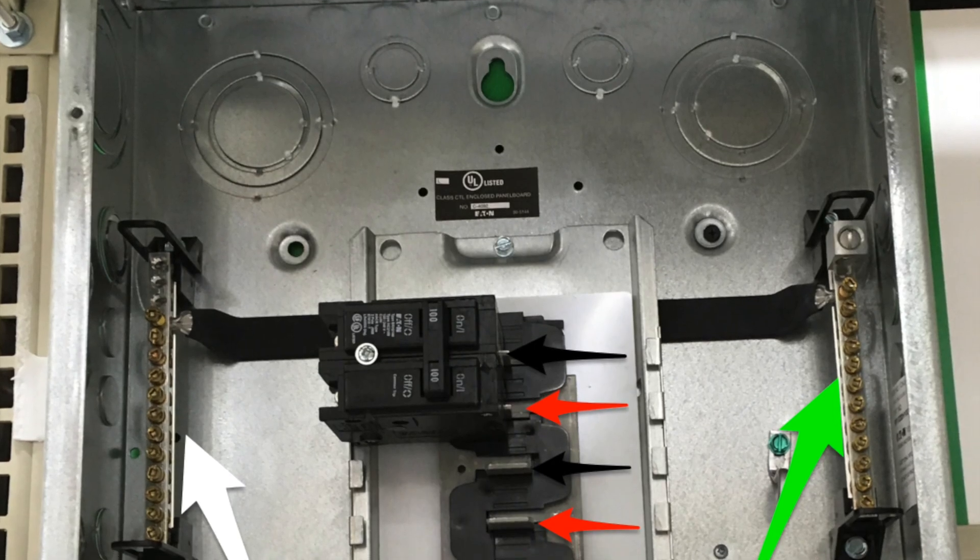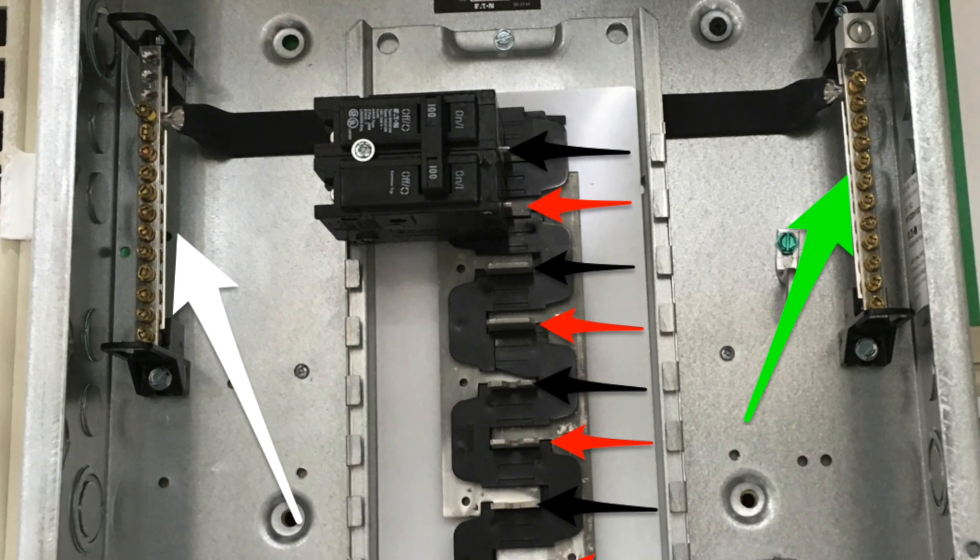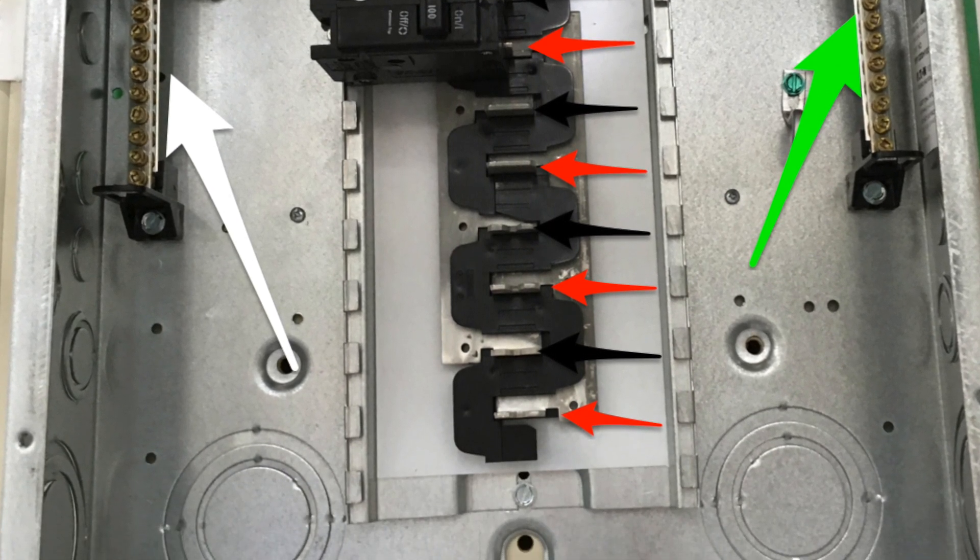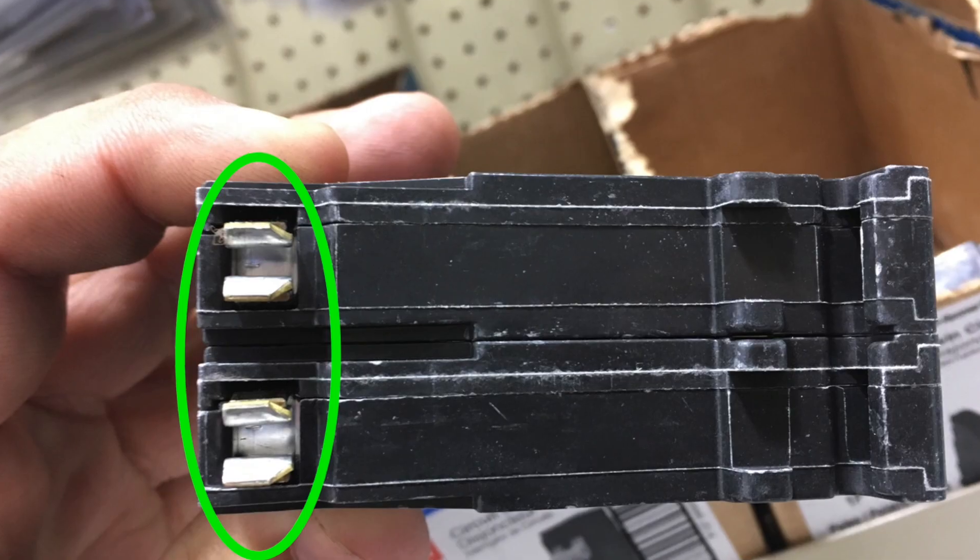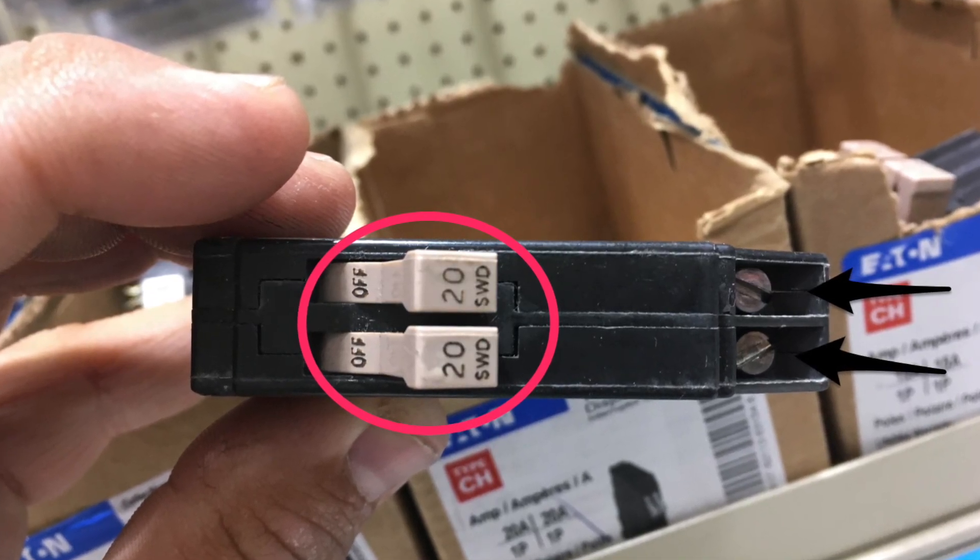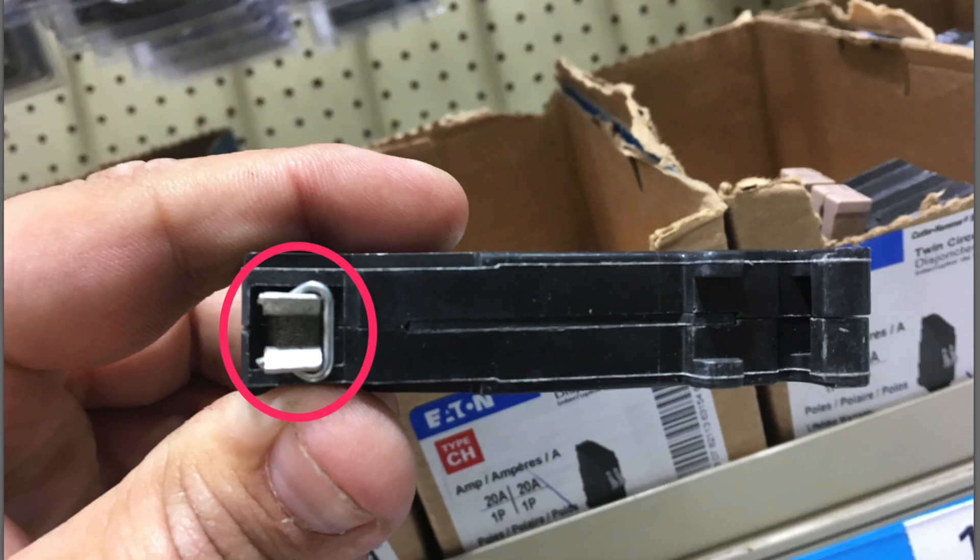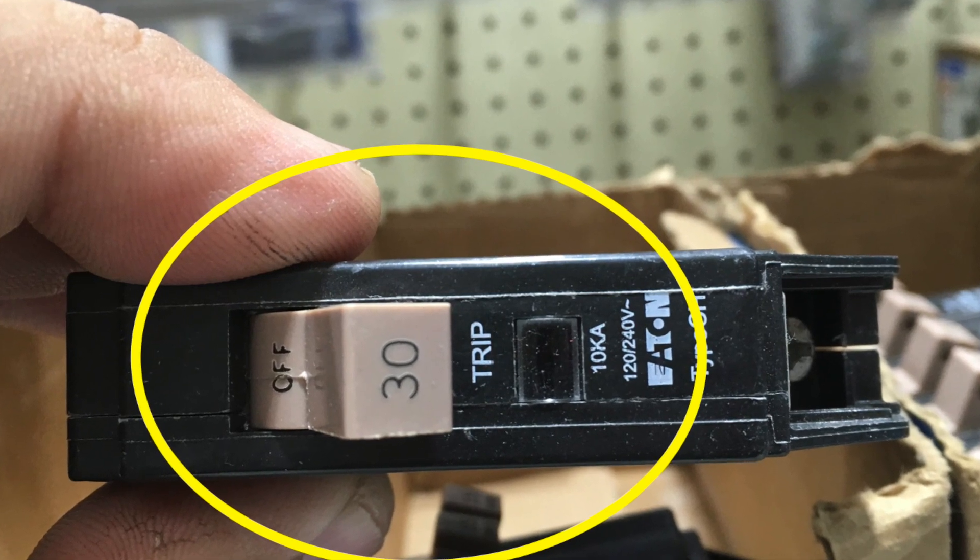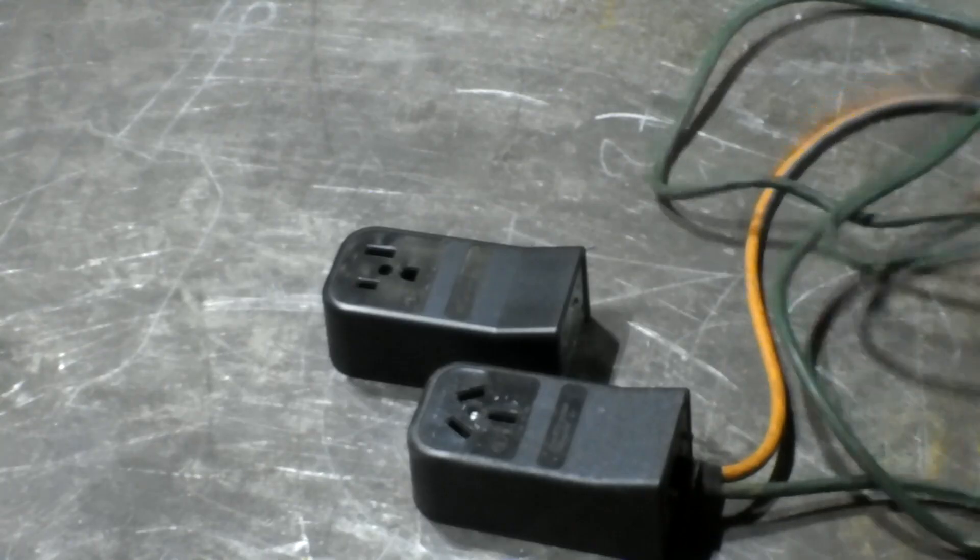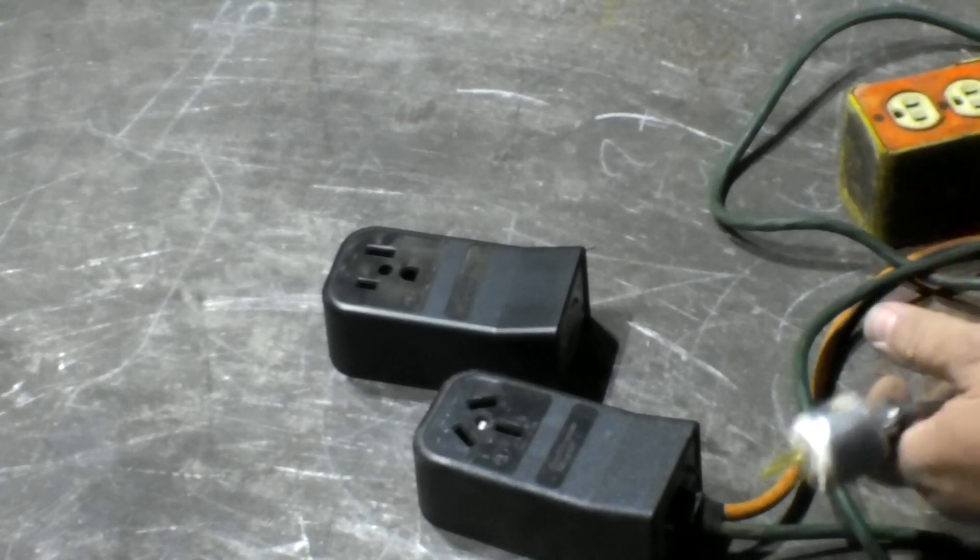So now of course you have to plug into two different 110 legs. As I mentioned earlier, there's an A leg and a B leg, and in order to get 220 these have to be on different legs, on different circuits. Two different circuits as far as one leg going into a black one and one going into a red one. That's why a double pole breaker with common trip is used for 220. This here is what it looks like, and this is the back side of it. Now don't mistake it for one of these breakers. These are two individual circuits but they are on the same leg. They only tie into one leg in the breaker box as you can see here on the back side.